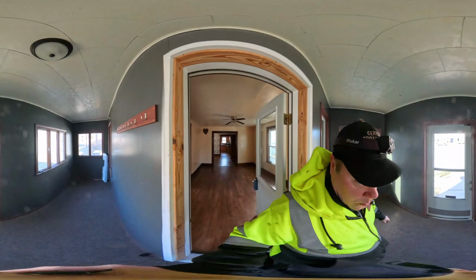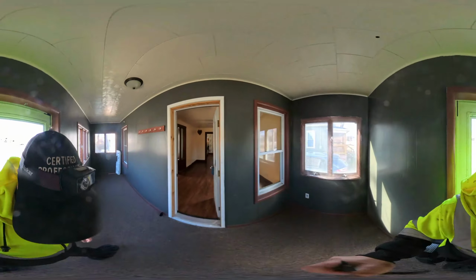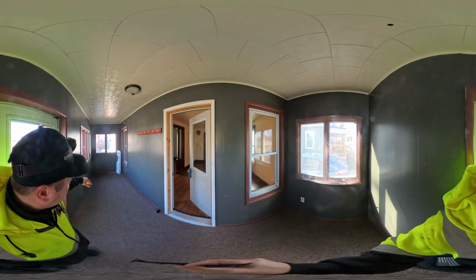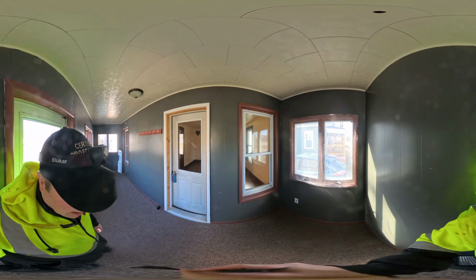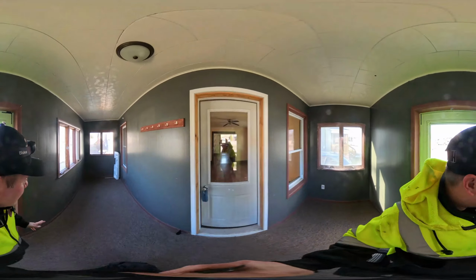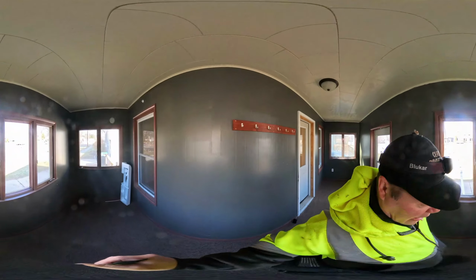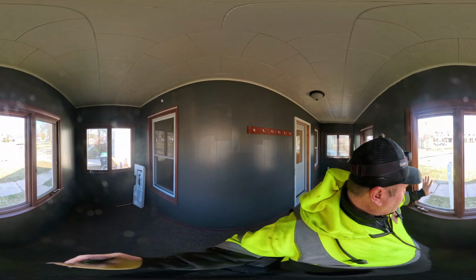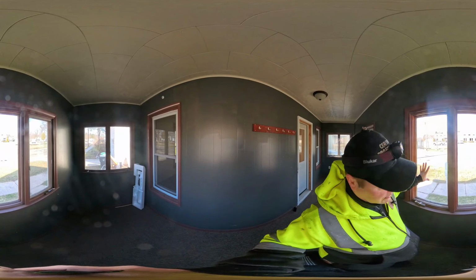We do have some open grounds and neutrals on the plugs throughout. I've only counted 2 out of the 20 that I've checked, so it's not that big of a deal - we can get that fixed. I mean, it is a big deal if you don't take care of it.